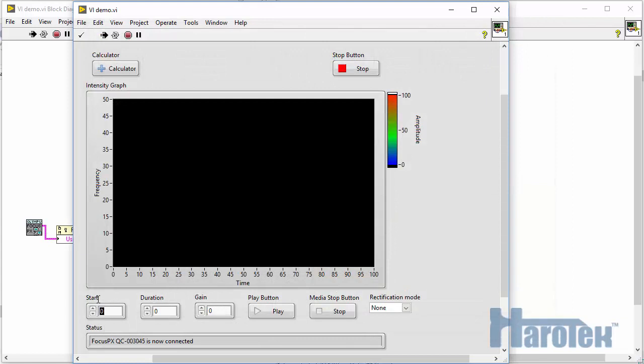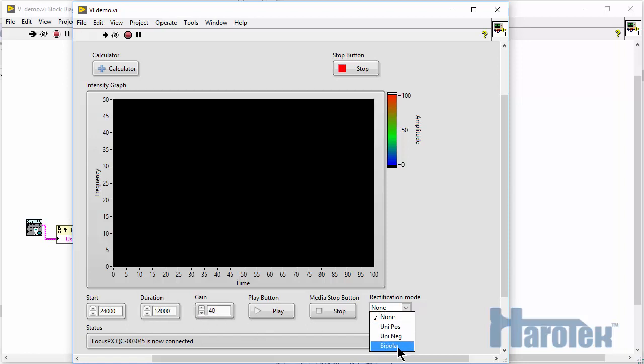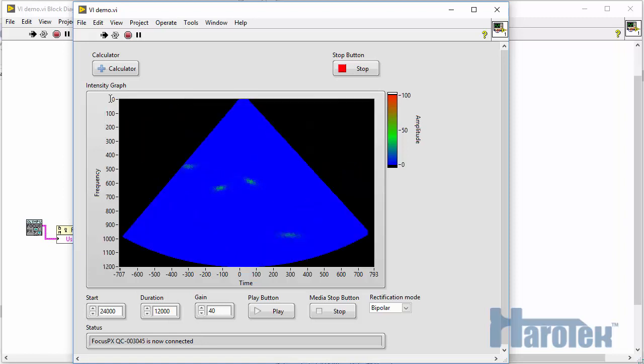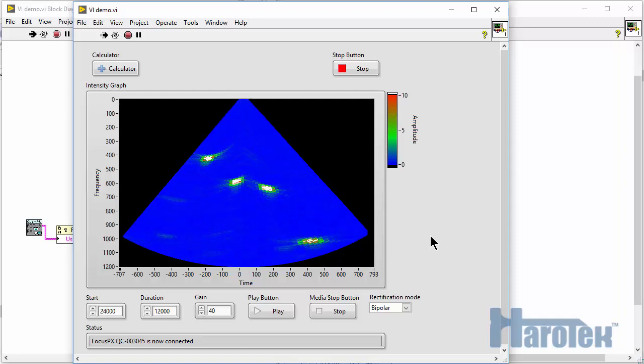Let's set the start and duration parameters of the ASCAN. Those parameters are in nanoseconds. The gain, the bipolar rectification mode, and let's start the acquisition. I invert the intensity graph, change the scale, and when I move the probe we can see that we have real-time acquisition.